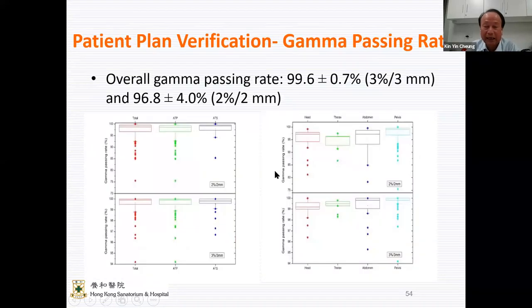And these are the gamma passing rates for the previous plans: 99% for a gamma criteria of 3% or 3 millimeter distance to agreement, and 97% for a passing criteria of 2% dose difference and 2 millimeter distance to agreement.